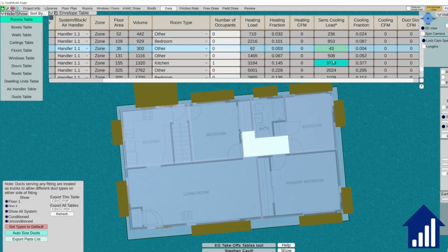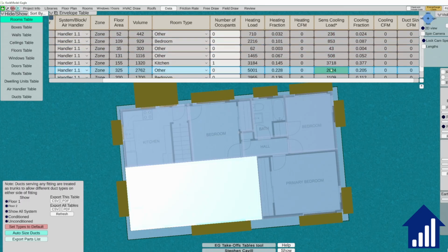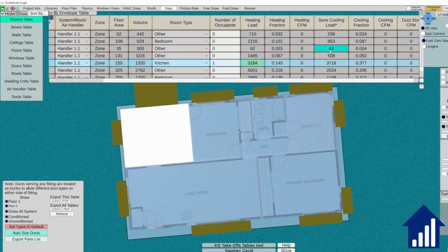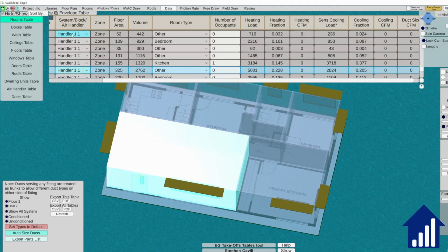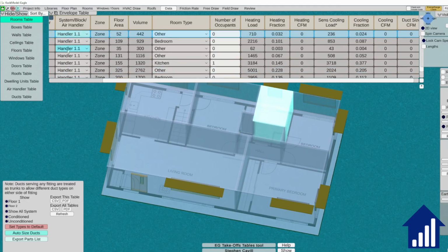So this would help us if we're going to be sizing ductwork. We need to look at both the cooling load and the heating load for the room. We choose the bigger number, and then we need to size our system and ductwork so we can deliver this much heat in the winter and remove this much heat in the summer. Folks, this is called an ACCA Manual J room by room heating and cooling load calculation. Okay? You need to get this done if you're serious about electrification and you're serious about a house that performs.